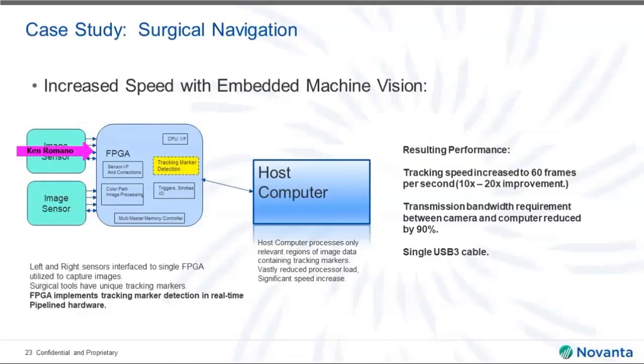So basically at the full frame rate of the image sensor, we're finding the candidates of what could be the marker. And we're just passing those candidate regions for the marker to the host computer. So you get a lot of benefits for speed and efficiency by doing that. So obviously, if you're just passing what looks like the markers on the tool, you're eliminating most of the image data. You're only sending the relevant regions of interest. And so you're increasing speed by sending a lot less data over that link. And then the host computer only has to look at those regions that are potentially the target. So its amount of CPU cycle processing is vastly reduced to where you're looking at only 10% of the data, for example, in the image, where you used to have to process and examine all of it.